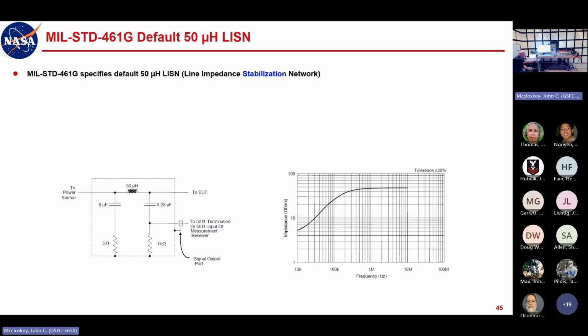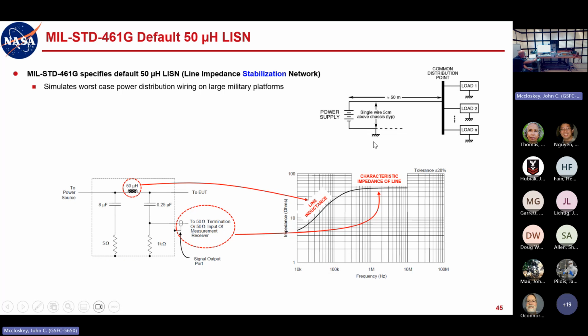Mil Standard 461 specifies a 50 microhenry LISN, and so you see the 50 microhenries is what's going to define the impedance at the low end. Then the high end is going to be that 50 ohm termination of your measurement receiver, which basically is going to be that shunt at high frequencies. So you have 50 ohms up here. This simulates the worst case power distribution wiring on military platforms, where you have a single wire about 5 centimeters above chassis, and structure is used as the intentional current return path, which we don't do on spacecraft generally.